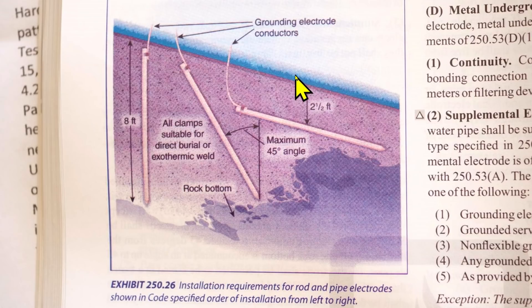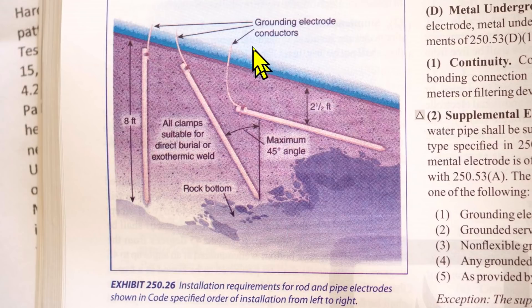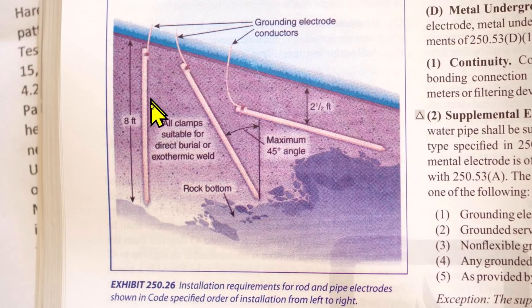Here we have another example of grounding electrode conductors. This is Exhibit 250.26 from the NEC handbook. You see these are wires going to these ground rods. This depiction shows different ways to put in ground rods. You can put it straight down — that's the most common — or you can put them at an angle.